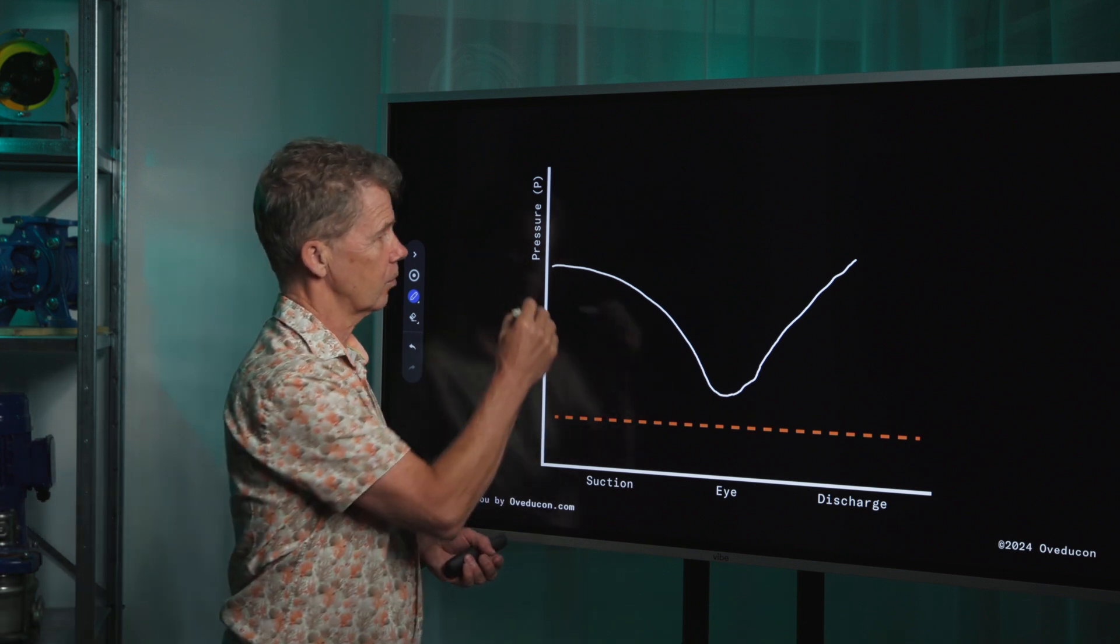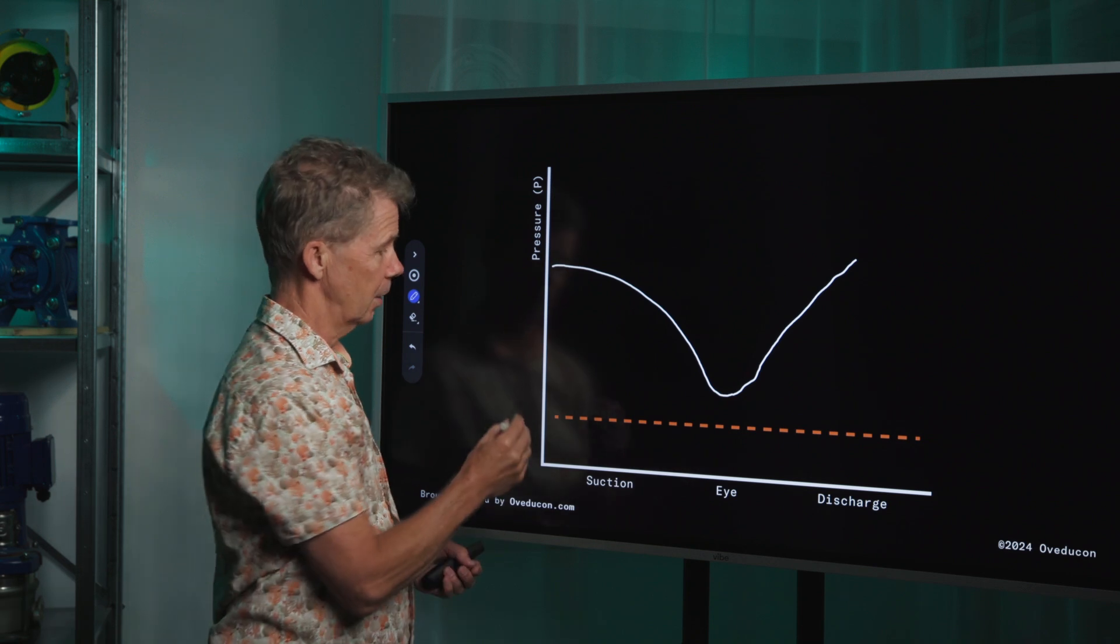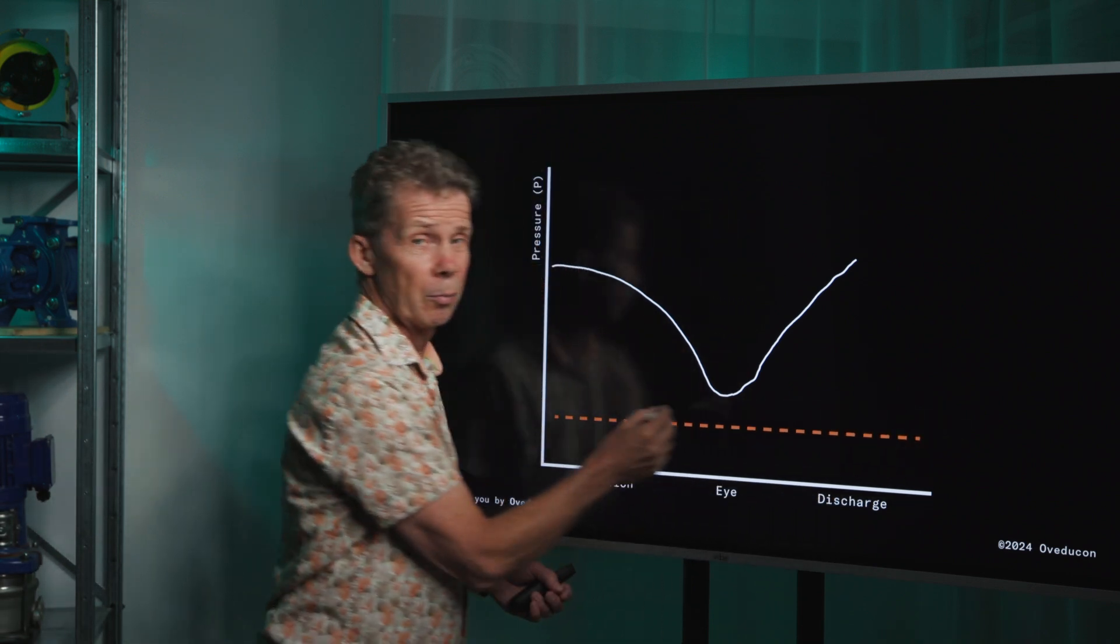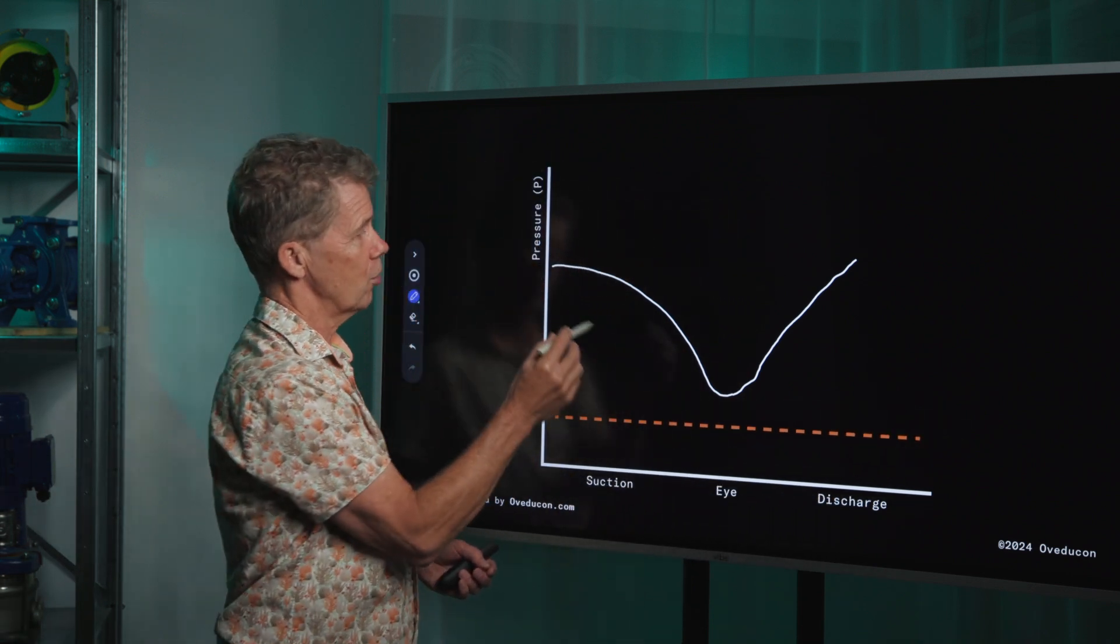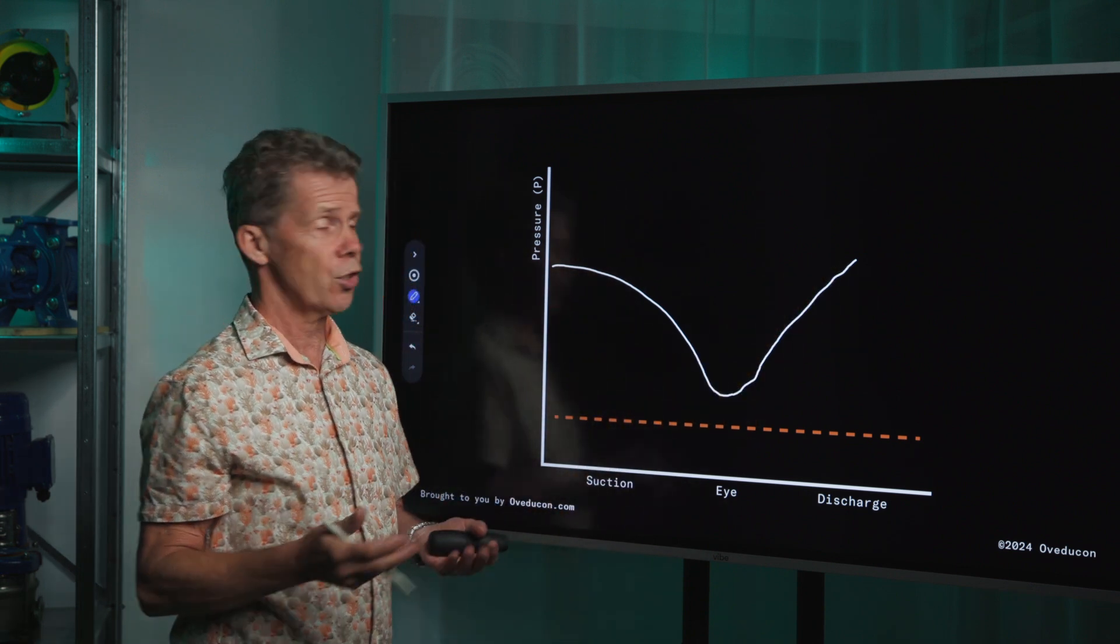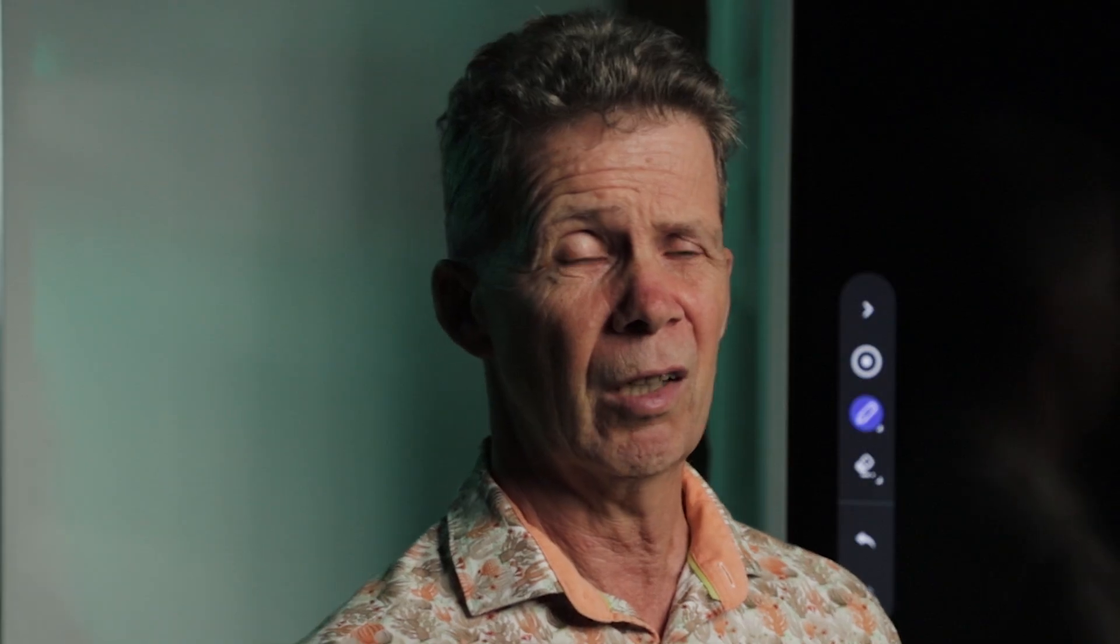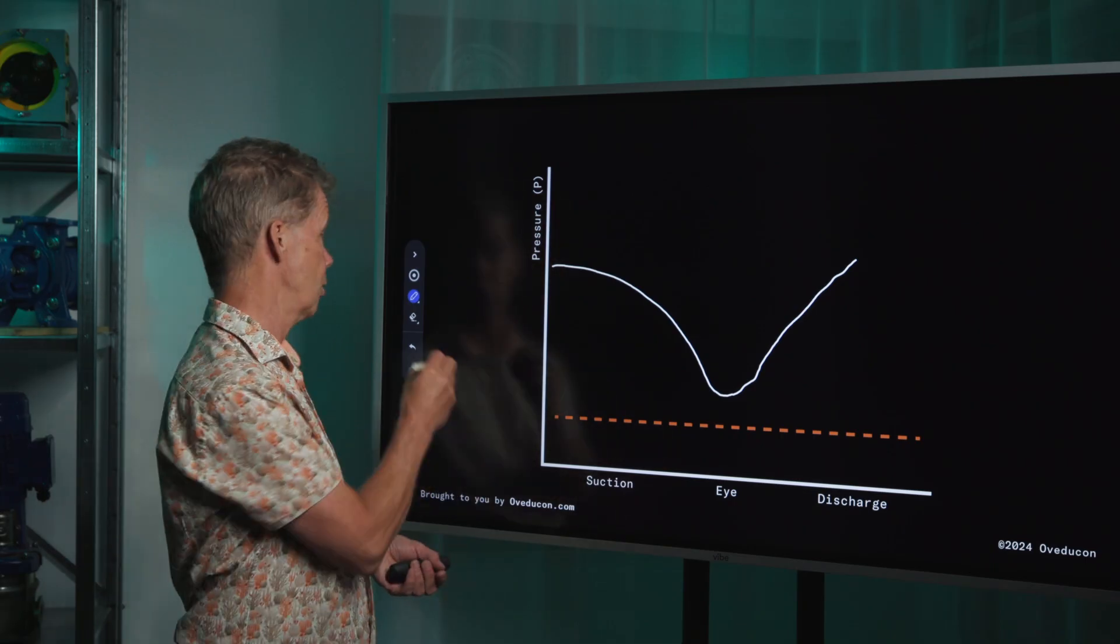In this case, this is the pressure, the suction pressure in your impeller. And this is the vapor pressure line. As long as the pressure in your suction stays above the vapor pressure line, no cavitation vapor bubbles are formed. So you don't have any cavitation.